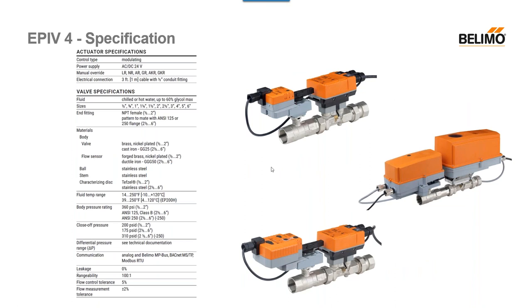This slide is a direct screenshot from the PGPL in the EPIV section. You'll see all different specifications you may need — materials, end fittings, electrical connections. This is a modulating valve and most specifications stayed the same from the EPIV3s. The main change is in the differential pressure range, which is valve-specific. Also note at the very bottom the flow measurement tolerance, which is plus or minus 2% for these valves — a really low number that I'll illustrate in a later slide.